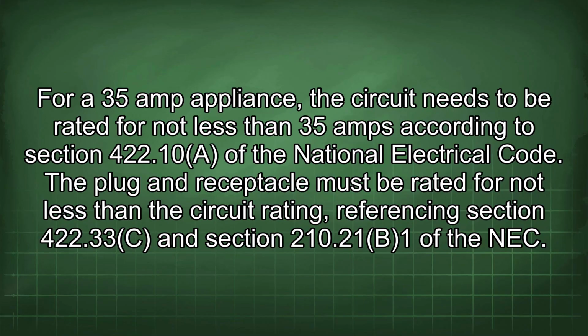For a 35 amp appliance, the circuit needs to be rated for not less than 35 amps according to section 422.10 of the National Electrical Code. The plug and receptacle must be rated for not less than the circuit rating, referencing section 422.33(C) and section 210.21(B)(1) of the NEC.